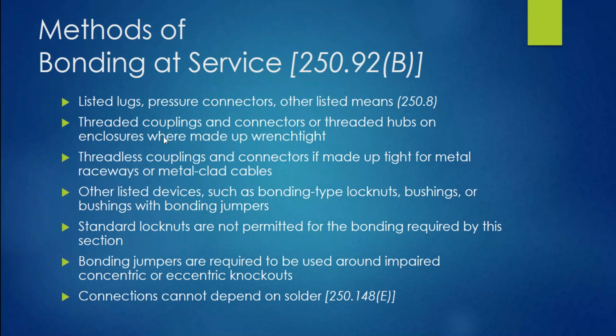Again, we kind of went over all these, but you can use listed lugs, pressure connections, other listed means that are in 250.8, which gives you a laundry list of methods. And you can use any of these methods, not just one method in 250.8. You can use all of them. Threaded couplings, connectors, as we've talked about. Threadless couplings and connectors, as we talked about. Other devices such as bonding type lock nuts, bushings, and bushings with bonding jumpers.